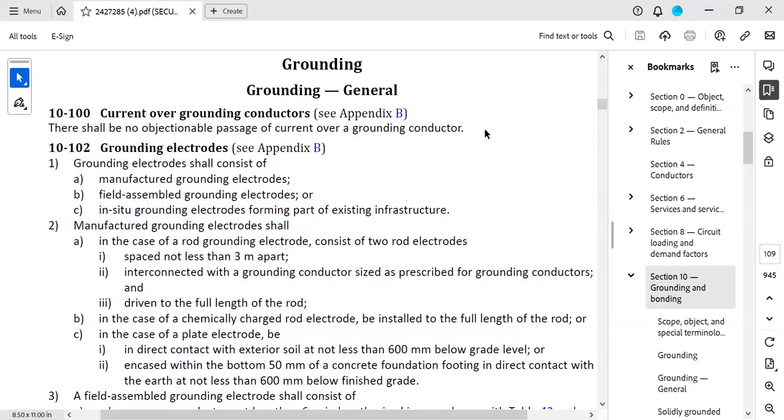That objectionable current flow can also happen in the grounding conductor when it's adjacent to another ground, too close to that other ground. In other rules about the grounding electrodes, it talks about how far away they should be. They should be three meters away because of this.